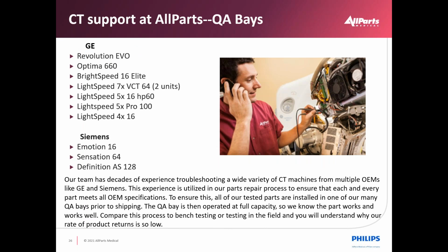And then finally, realize that AllParts not only does parts harvesting, but repair operations has QA bays to validate testing and image quality on parts that are repaired. So these systems are also leveraged for training. In the GE space, we have the Revolution EVO product, Optima 660, Brightspeed 16, two Lightspeed VCTs, one with the older VDAS, one with the newer HDAS, and then we have the 5X HP60 system, the 5X Pro 100 for high power X-ray generators, and an older Lightspeed 4X system. That product was released in 2002, so 19 years ago to be exact now. So there's a spread of systems in the GE space.